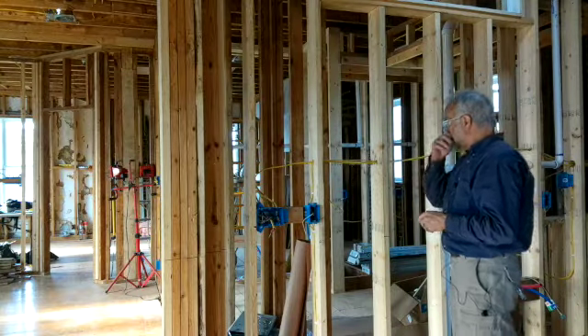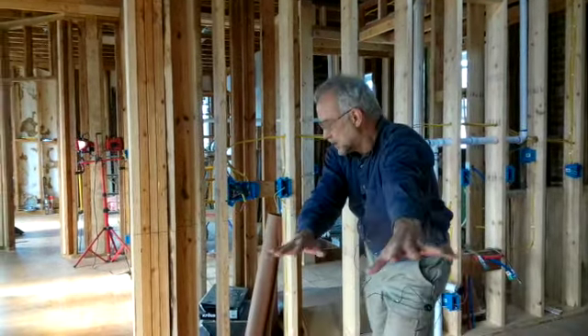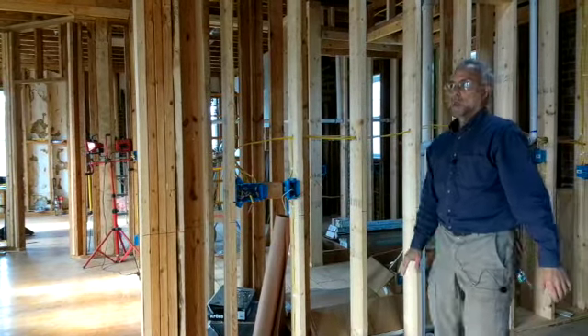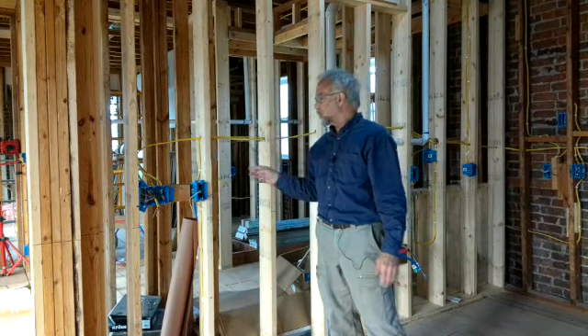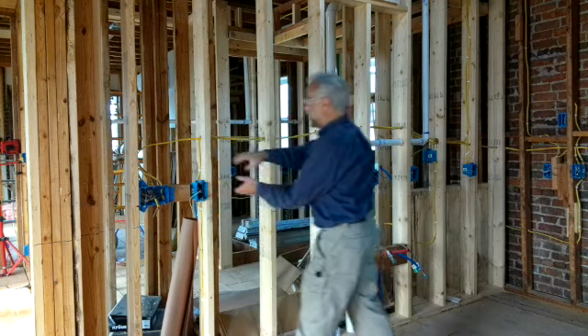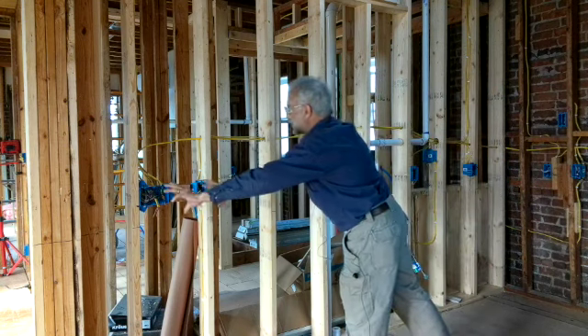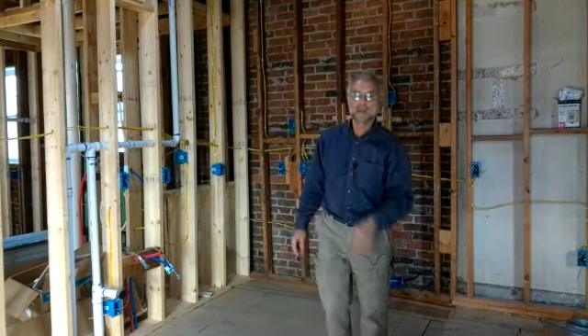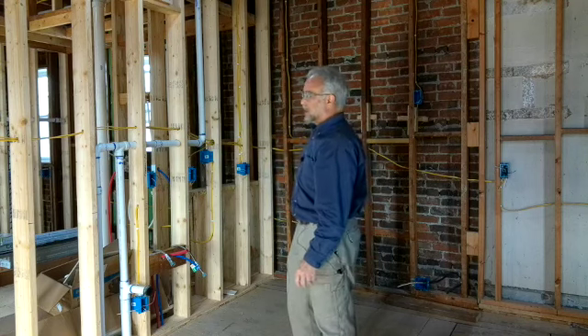So, for example, in here, I mentioned the countertop lights. There's going to be a peninsula going across here, so this will all be countertop like that. Code says that you have to have 2 sets of circuits for plugging things in around the countertop. So even if it's a short wall or something, you still have to have 2 circuits. So one like this, and I've got another one way over here. And that's simply because there are so many appliances. Either the sink on each side, there has to be an outlet. So there's a lot of mandated wiring by code for a kitchen.